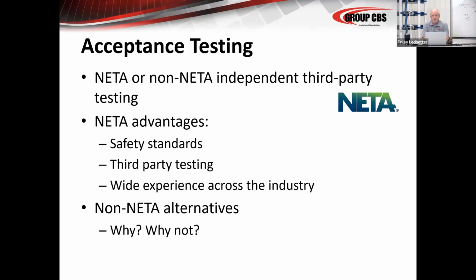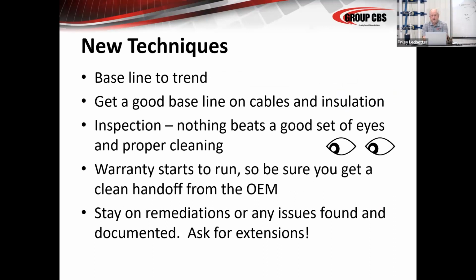Quite often, the equipment is not in a new facility. It's simply a new piece of gear going into an older system. How it interacts with the older system and how the two work together is very important. So there are reasons to pick a non-NETA testing company to do your acceptance testing. And there are reasons to pick a NETA testing company. And all that needs to be factored in, and that decision needs to be made way in the beginning. Baseline to trend is what we're talking about.